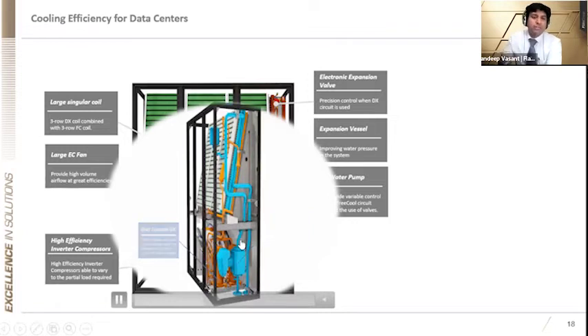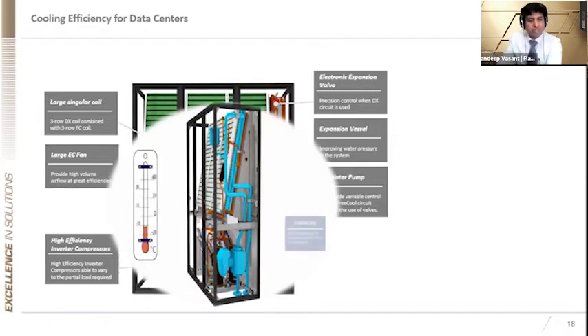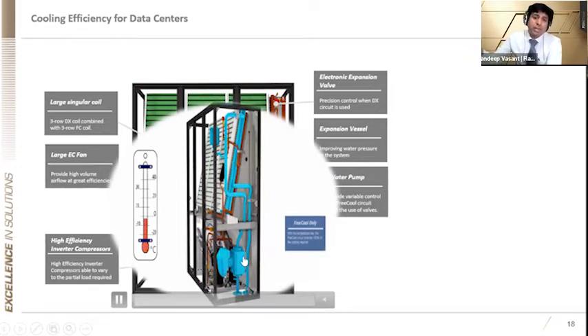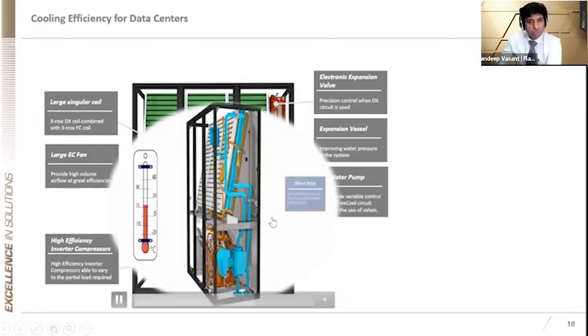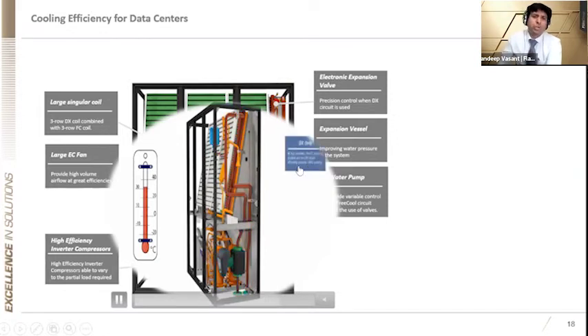So let us say the ambient is very low, like in Bangalore or wherever there are extreme weather conditions, like November, December, very low. Obviously the free cooling circuit would operate. In this technology, we restrict the movement of bad air into the data center. As the ambient increases, it goes into mixed mode. What is mixed mode? Partially this circuit and partially the DX and the chilled water. Temperature very harsh, very high, obviously it goes into DX mode. So this is an indirect free cooling technology which can also be implemented.